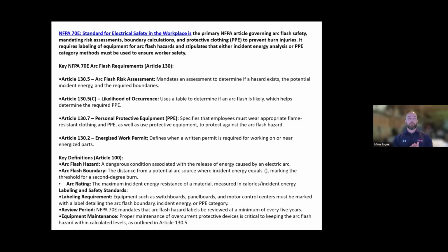In certain locations, especially in switchgear, the cal ratings tend to rise. Our suits are rated up to 40 cals, and they make suits rated up to 100, I believe 120 cal. Anything above 40 cal is considered a danger standard, which includes switchgear, certain switchboards, and all transformers — that stuff cannot be worked on live, which is why we have to wear these suits. That's why these labels are so imperative, to tell us exactly what to wear and what kind of PPE is proper.